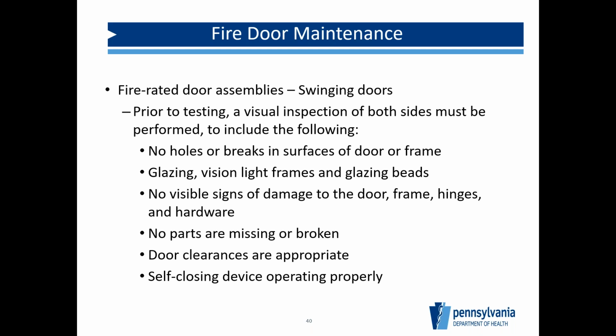This is right out of NFPA 80, in case anyone wants the basics of what we're looking for: no holes or breaks, visible signs of damage, missing or broken parts, and door clearances. I don't have them all listed here because clearances differ depending on whether it's a metal or wood door, or double doors—but there is a set of clearances. They actually make gauge tools you can buy online that have all the dimensions on them, so you can stick the gauge into the door gaps and check if your door is compliant.